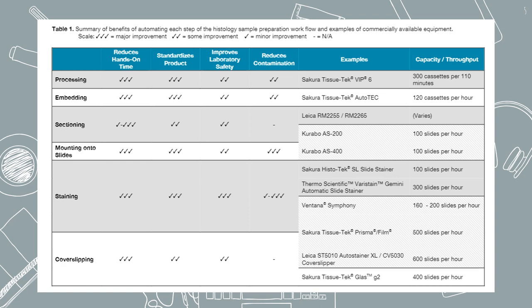This table shows the summary of benefits of automating each step of the histology sample preparation workflow and examples of commercially available equipment. For example, for processing, the Sakura Tissue-Tek 2 VIP 6 has a capacity of 300 cassettes per run. With this machine, hands-on time is greatly reduced since the machine does all the work. It standardizes the product, improves laboratory safety, and reduces contamination as well.